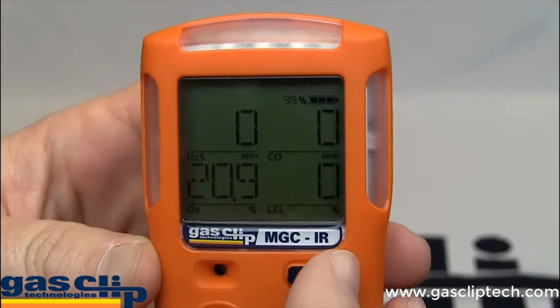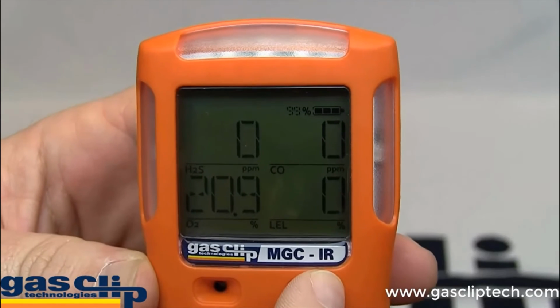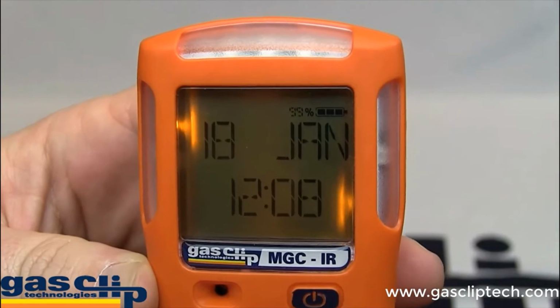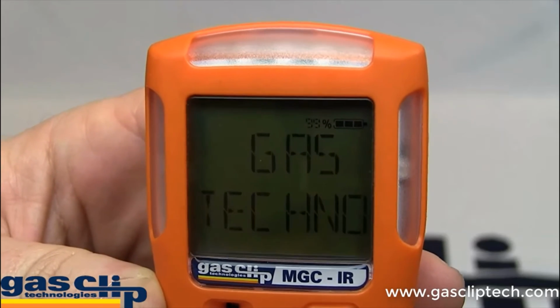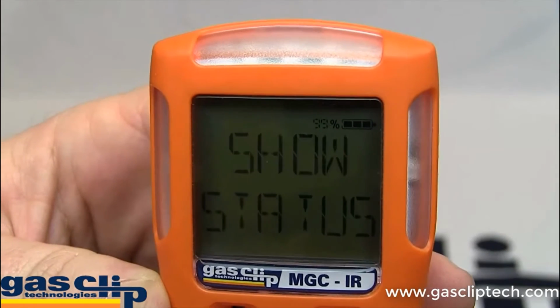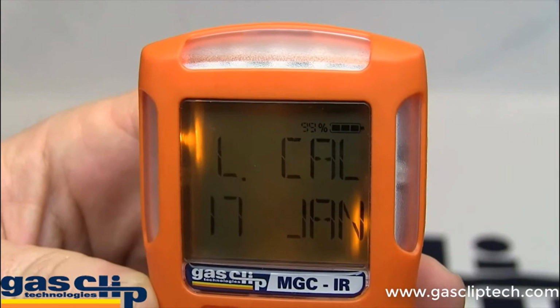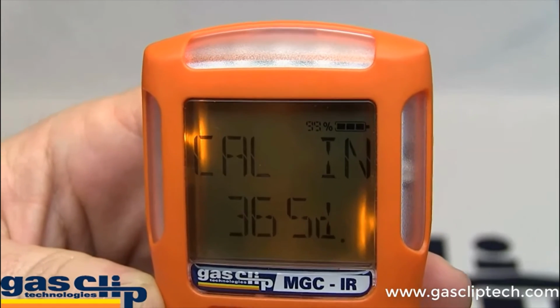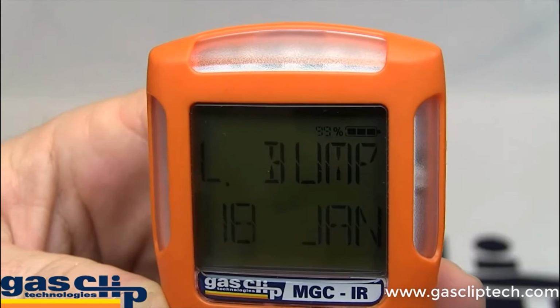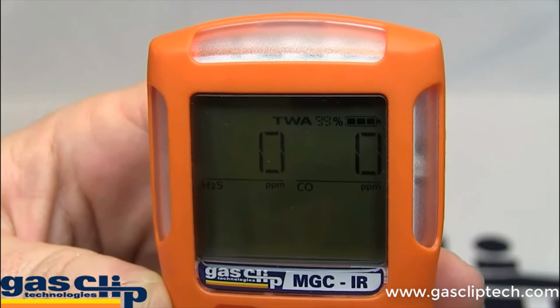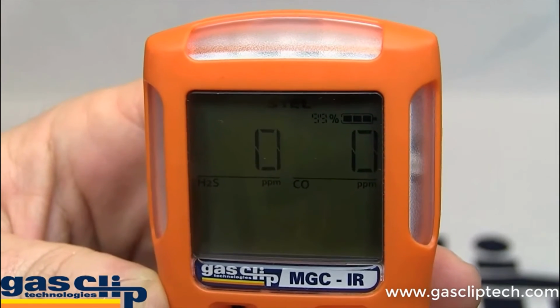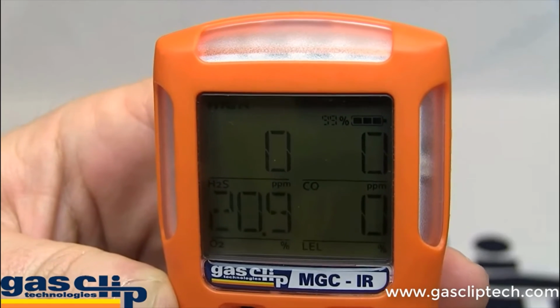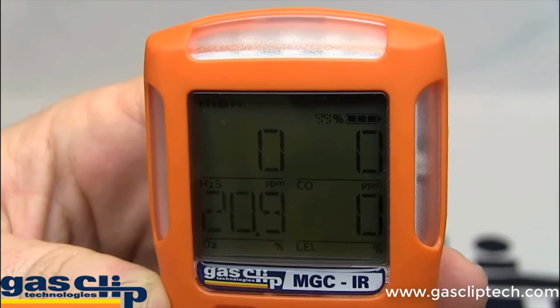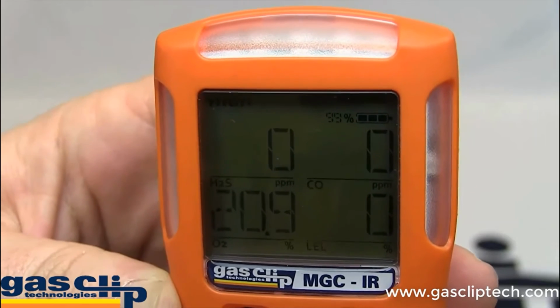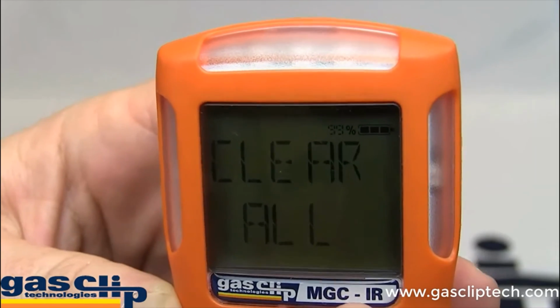To access the show status menu, simply double tap the power button. It will show the date and time, and any message that you have put on the monitor. When it says show status, simply press the power button. It will show your last calibration, your last bump test, your TWA and STEL screens, and finally your peak reading screens. It will give you the option to clear readings. To perform this, simply press the power button.